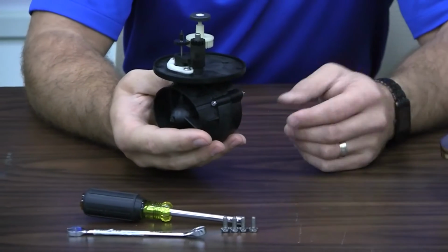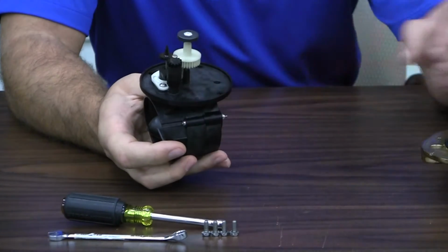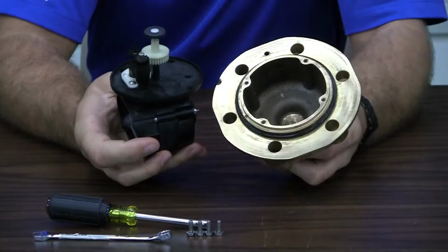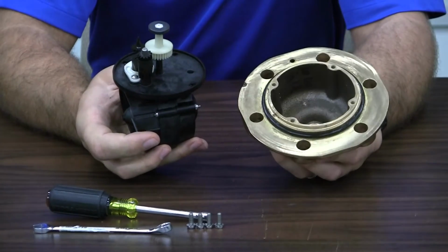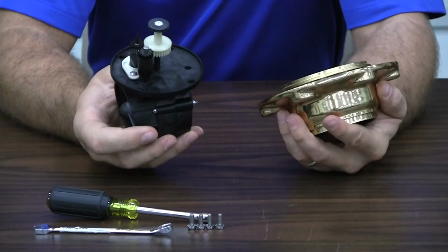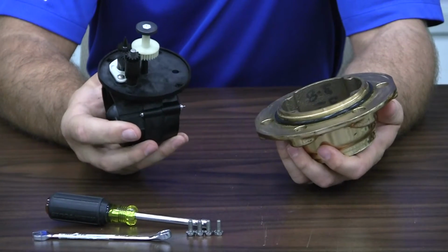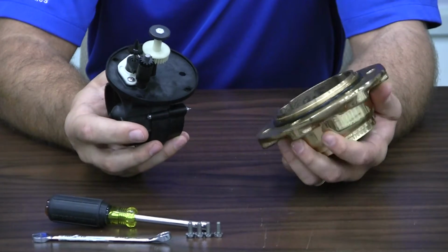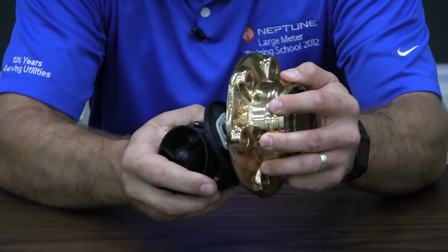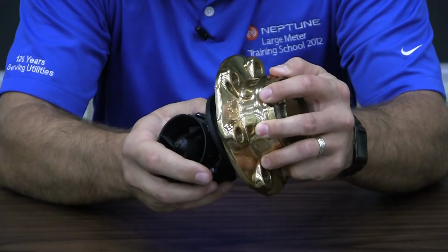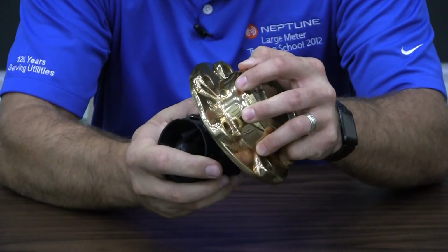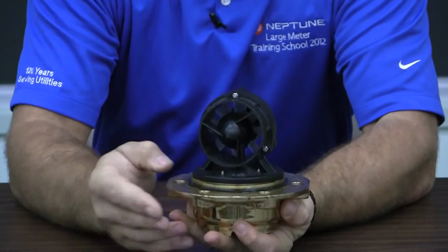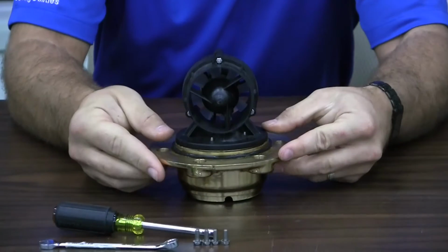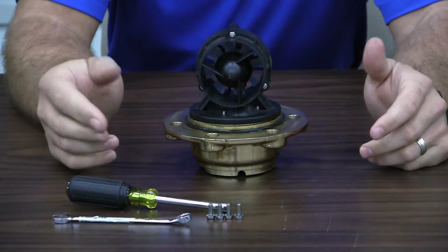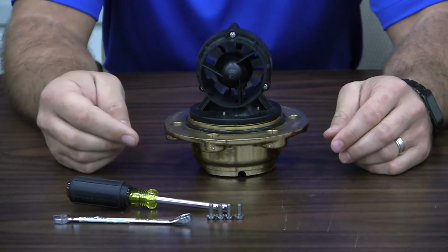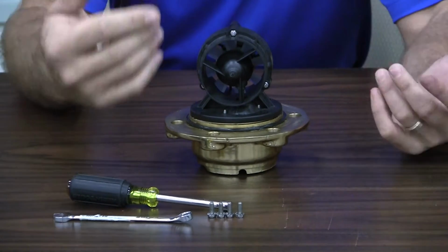Now we have to get our turbine element back inside of our cover. This post here is actually going to align with the machined hole inside of our cover. And if we look inside the cover, there's also a gear, and that gear is going to mate with our calibration gear. So when you're placing the turbine element back into the cover, make sure that that machined hole and the post of the calibration gear align. At that point, we have our turbine and our cover put together successfully. We have to put the 4 bolts back in, and then we'll be ready to put it back into the main case.